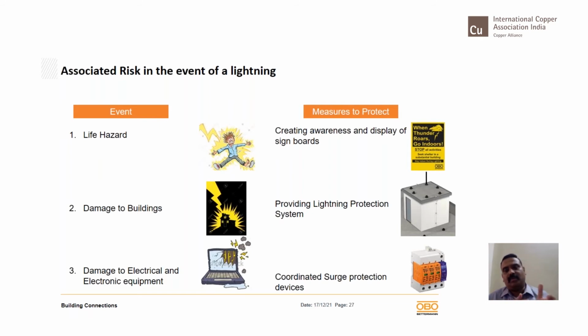Now, to clearly understand what I have told till now, to summarize, there are 3 important aspects. The first aspect is protection of human life, which comes purely by awareness, giving them an idea to stay inside a building and not to touch any metallic object during that time. The second point was to protect the building. That building protection should go with a proper lightning protection system. I utter this word proper because just having one spike on a building and saying that it is fulfilling the statutory need may not suffice. You need to calculate the size of the building, and there should be a sufficient number of conductors and down conductors. Then protection of electrical and electronic equipment comes purely by providing surge protection devices. These surge protection devices are the ones which are going to completely protect the electrical and electronic equipment from failure, even if you have an external lightning protection system.